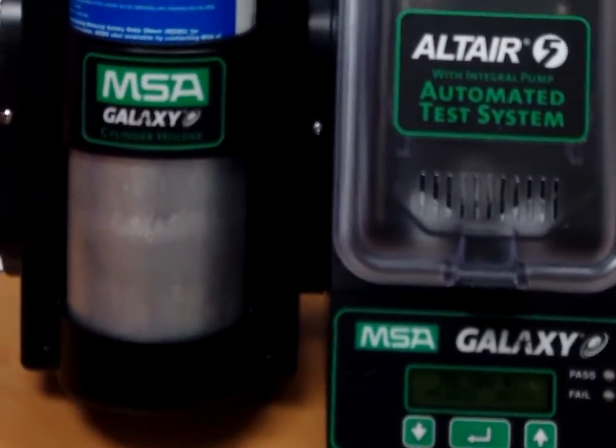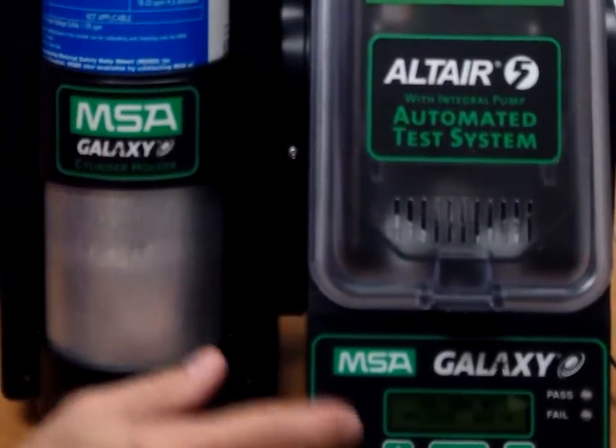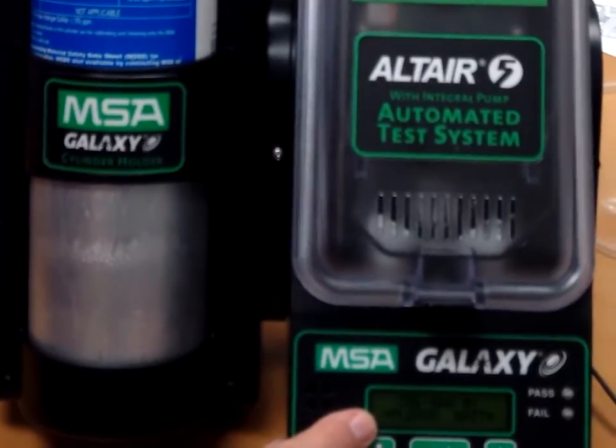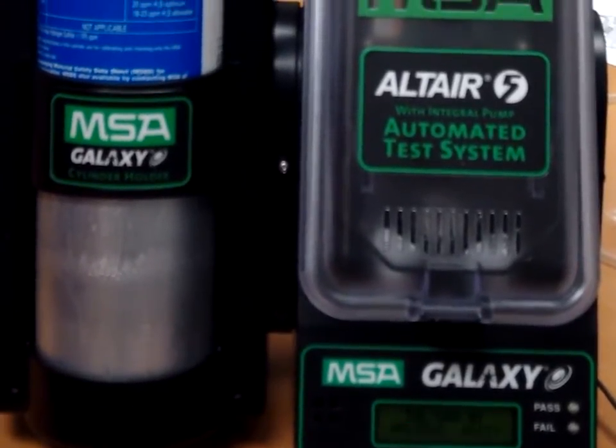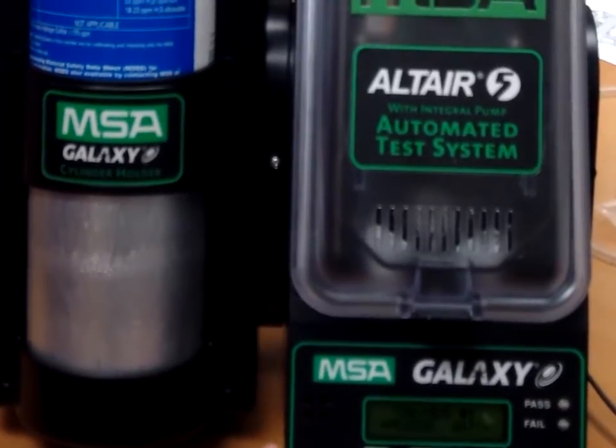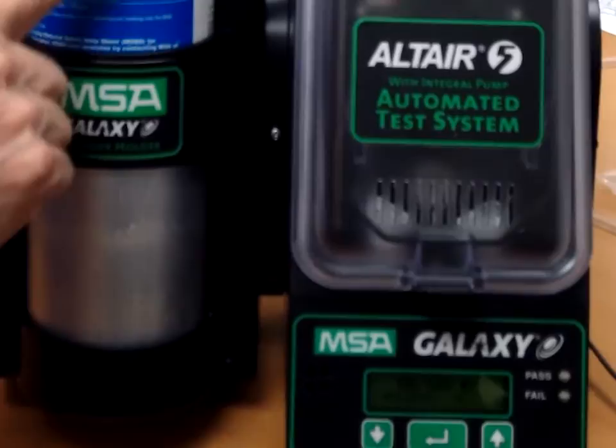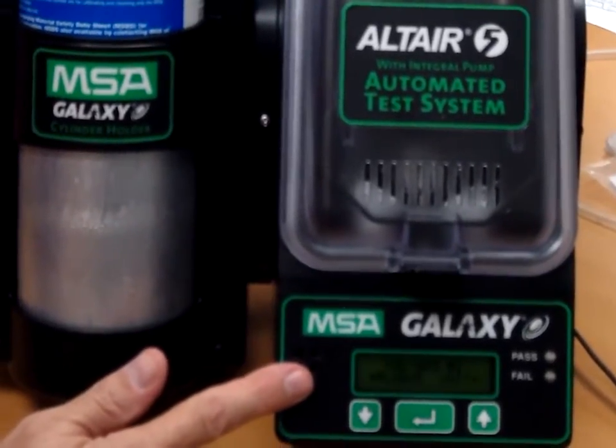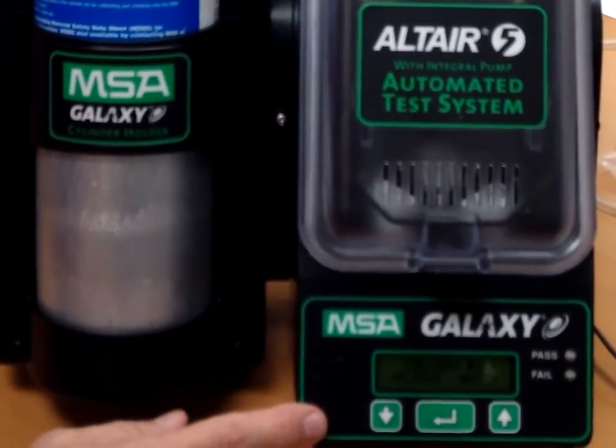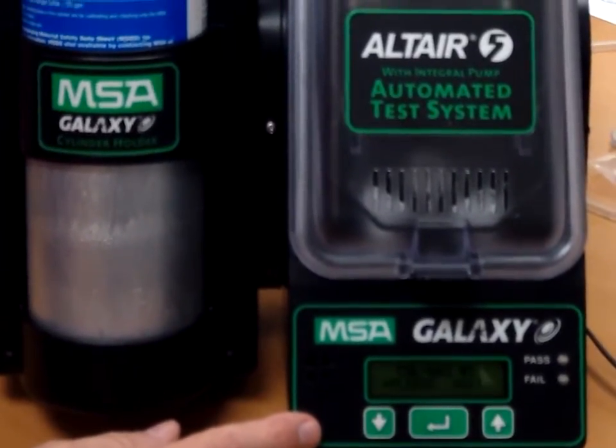Cal gas number 1 is going to read across that, and that's what we have here. At this point now, the gas is traveling through the unit, and you can see these numbers change. Right now we've got 20 on the H2S, 58 on the LEL, 15.3 on the O2, and 57 on the CO. If you look at these numbers right here, you can see the ranges that you want to be in. You can see that we're already in that range. So what will happen in just a few moments is that the calibration will be complete, and then we'll see that check mark on the screen.